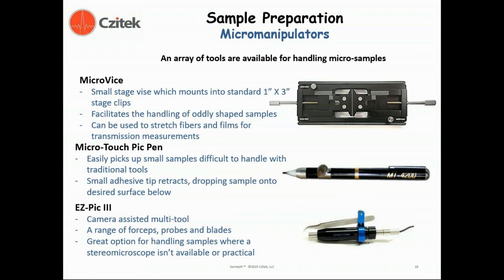Other miscellaneous tools can help simplify analysis. A microvise is useful for holding an oddly shaped sample in a particular orientation — it grips the sample and interfaces into the standard one-by-three-inch stage clip. The microtouch pen allows you to pick up small samples with a very small adhesive tip; when the tip retracts, the sample drops onto the desired surface. If your hands are not steady, various micromanipulator options incorporate imaging as part of the system, and more expensive solutions can completely automate the process of moving and transferring extremely small samples.